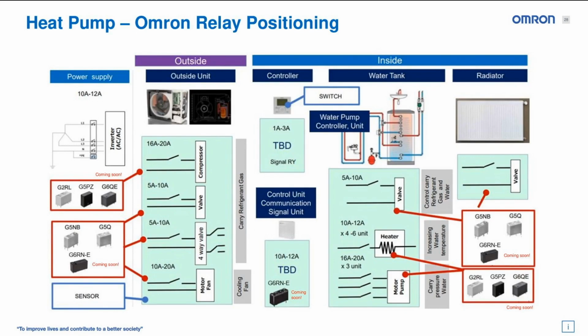But once we get inside the water tank, we're talking about valves once again. We're talking about heaters. We're talking about motors and pumps, which can all use similar relays. So for valves, once again, we're looking 5 to 10 amps, and that would be the G5NB, G5Q, and G6RNE. And for the higher power items like heaters and motors, we're talking about the G2RL, G5PZ 20 amp sealed relay, and the upcoming G6QE. So the products that we already have support the functions that require switching within the end products like heat pump and traditional HVAC and refrigeration.